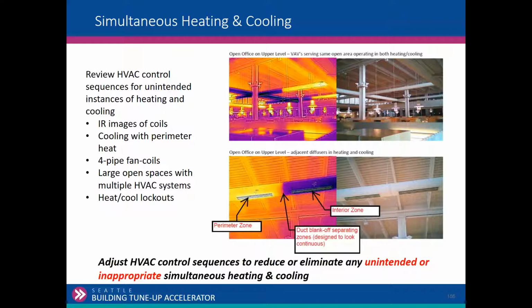Now, a VAV system, this is working correctly. A VAV system is designed around perimeter and core zones, so there's nothing wrong with this picture. At the code level, I've been involved with code development. We've been trying to figure out how to minimize this. In fact, in the new Seattle Energy Code, Washington State Energy Code, we're trying to implement deadband in zones that freely communicate with each other. These are two temperature zones, perimeter and core. So we thought we'd be smart and wrote language into the code that said, if you're building a new building, we don't want this, or we want to minimize this. So if it's a new building, we don't want you to energize heating in the perimeter zone until it's 5 degrees colder than the core. And in the core, we don't want you to implement cooling until it's 5 degrees warmer than the perimeter.